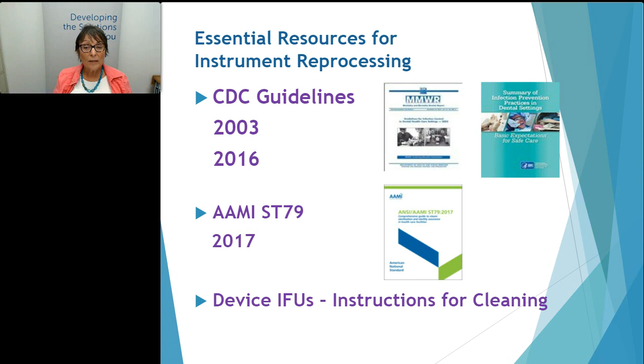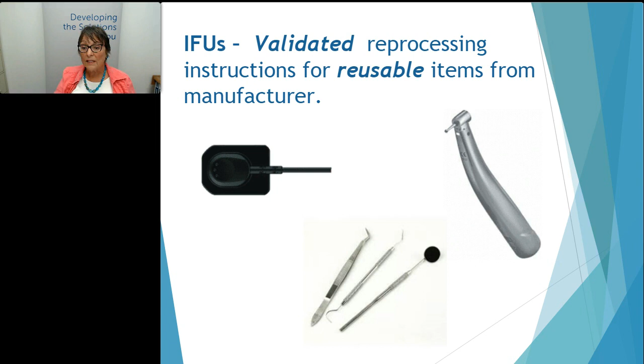So the manufacturer of this dental handpiece that you see on your screen, they cannot sell this device to you in the dental office until they have cleared it with the FDA. In order to clear it with the FDA, they have to show reprocessing instructions that do produce a clean handpiece, clean and sterile, and free of a certain amount of pathogenic organisms. They have to contract with labs to do that. It is an expensive process, and it is very complicated. But once the instructions are validated, then that means that you, the purchaser and end user, must follow those instructions to ensure that that device is safe for the next person that you're using it.